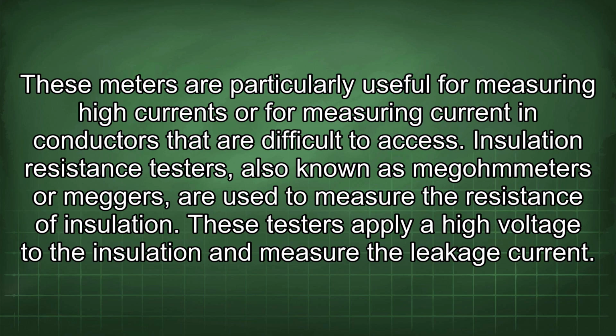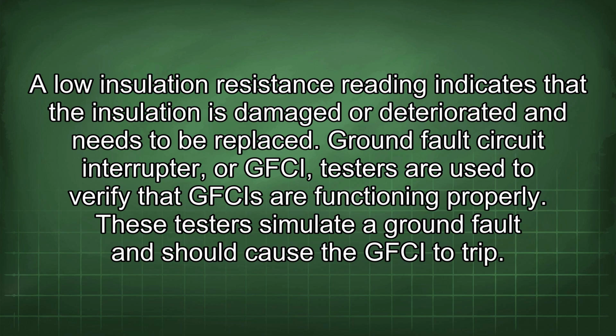Insulation resistance testers, also known as megohmmeters or meggers, are used to measure the resistance of insulation. These testers apply a high voltage to the insulation and measure the leakage current. A low insulation resistance reading indicates that the insulation is damaged or deteriorated and needs to be replaced. Ground fault circuit interrupter, or GFCI, testers are used to verify that GFCIs are functioning properly. These testers simulate a ground fault and should cause the GFCI to trip.